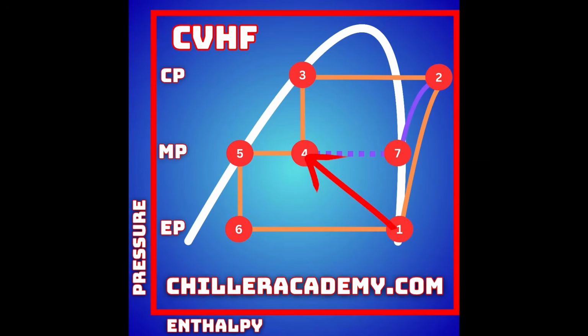This split is where the economizer's job is done. So from 4 to 5, 5 is the liquid that's left in the bottom of the economizer. From 4 to 7 is the vapor that gets sent back to the compressor and adds to that heat that you see at point 2. So this is our economizer line getting sent back to the compressor. Okay? This is where it gets blended.